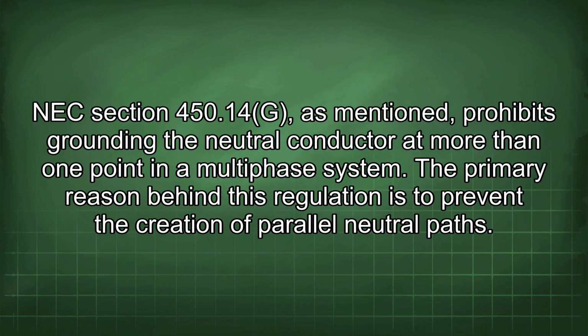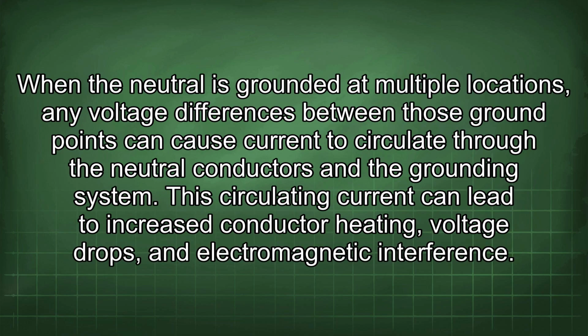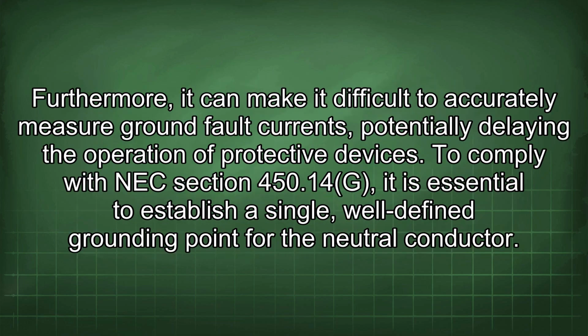NEC Section 450.14g, as mentioned, prohibits grounding the neutral conductor at more than one point in a multi-phase system. The primary reason behind this regulation is to prevent the creation of parallel neutral paths. When the neutral is grounded at multiple locations, any voltage differences between those ground points can cause current to circulate through the neutral conductors and the grounding system. This circulating current can lead to increased conductor heating, voltage drops, and electromagnetic interference. Furthermore, it can make it difficult to accurately measure ground fault currents, potentially delaying the operation of protective devices.